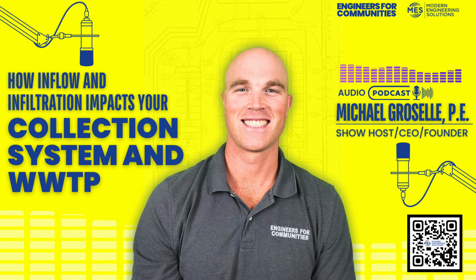All right, so where does it come from? Here I've got a good picture that demonstrates a lot of things. So a big infiltrator is stormwater pipes. This can come in sort of cross connections, illegal connections. You can see here like you've got a roof drain connection, foundation connection. You got breaks in the line, so water seeping through the ground into the pipe, roots busting the pipe up. You could have a manhole lid that isn't sealed all the way. Right here, you can have cracks or seals that aren't good in the manhole. And yeah, here's another image of cross connection.